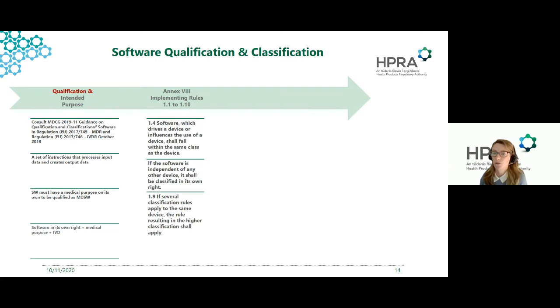So implementing rule 1.4 is only applicable for software which drives or influences the use of an in vitro diagnostic medical device. This rule should also be considered at least as an orientation for finding the right classification of software which is placed on the market in combination with a hardware medical device.